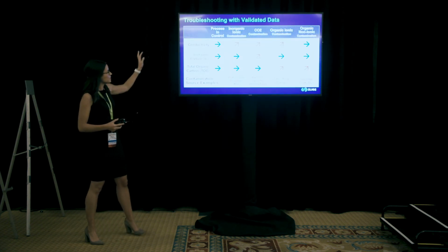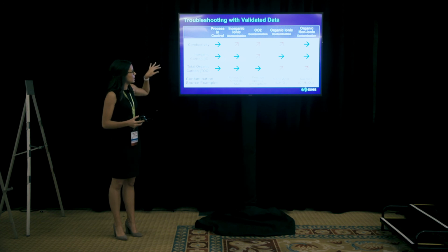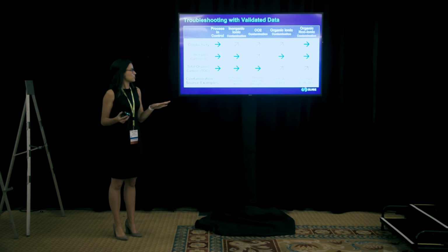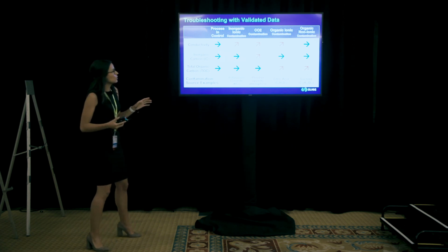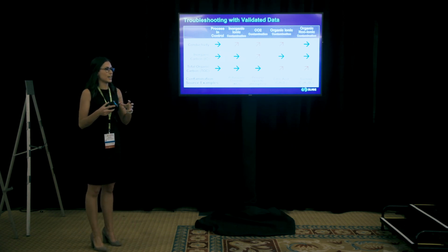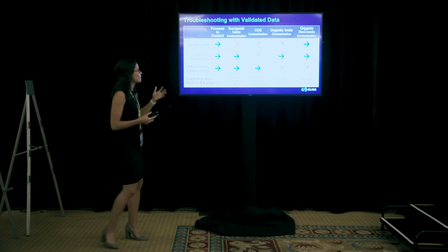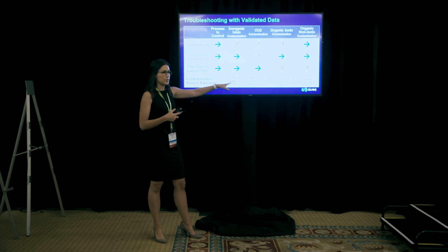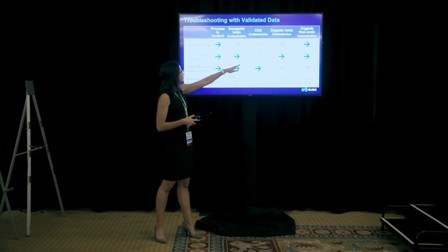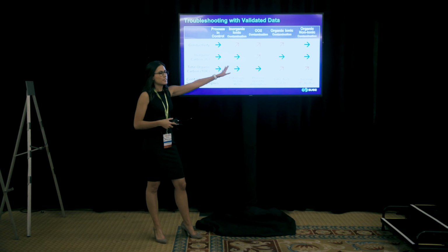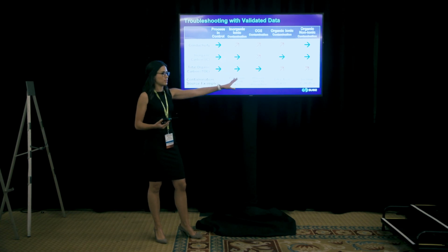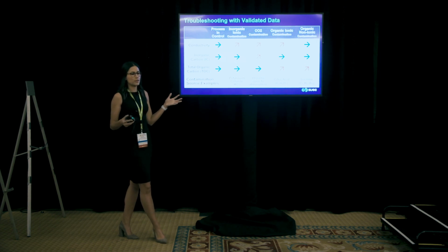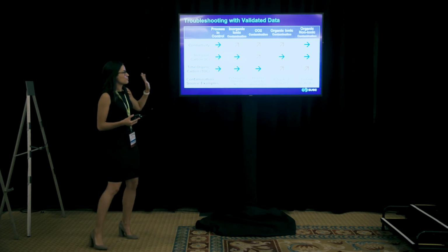So this is conductivity in the top row, inorganic carbon, total organic carbon. These are all 3 metrics that you will get from the instrument. So using these 3 data points to kind of triangulate what's happening in your system. I won't go through all of them, but for example, this one, where your total organic carbon is within your control range, but your inorganic carbon and your conductivity is increasing. This could indicate some CO2, atmospheric CO2 somewhere, so potentially your process is open to the atmosphere. So it helps you troubleshoot. So these are all 3 really important things.